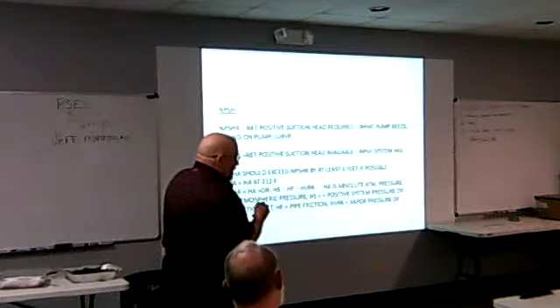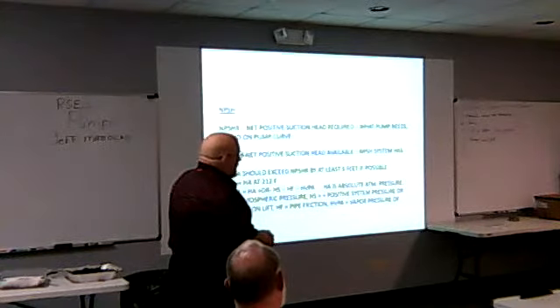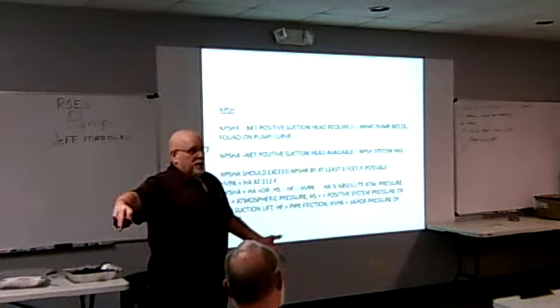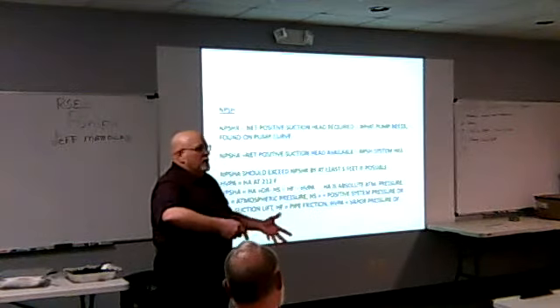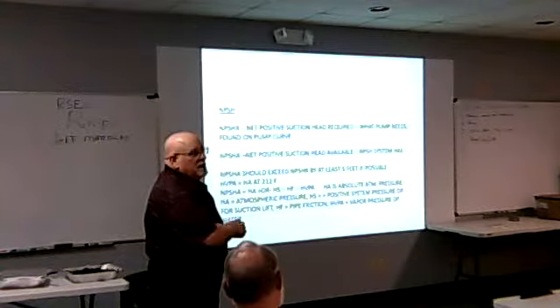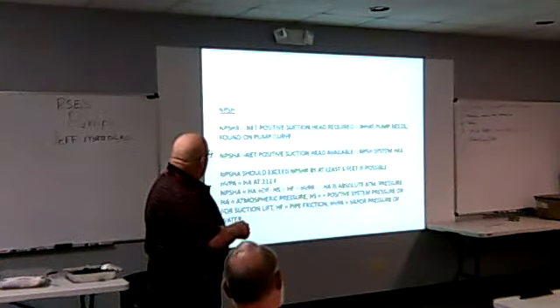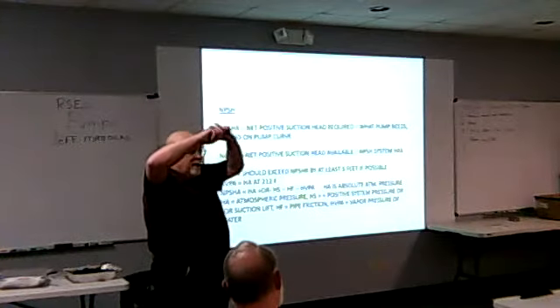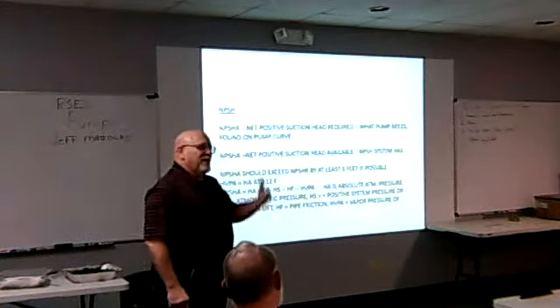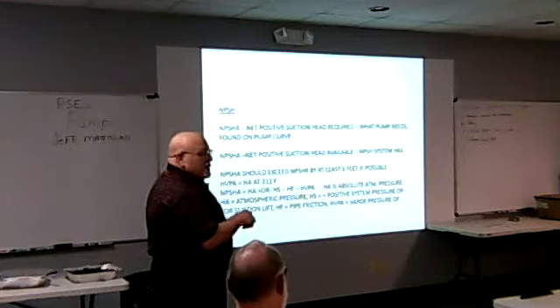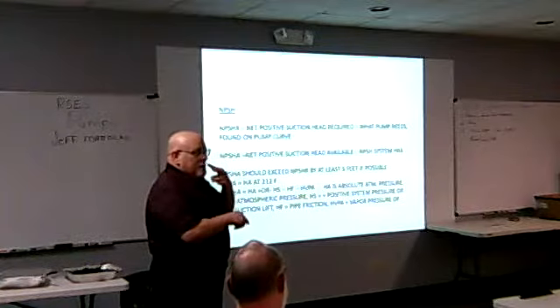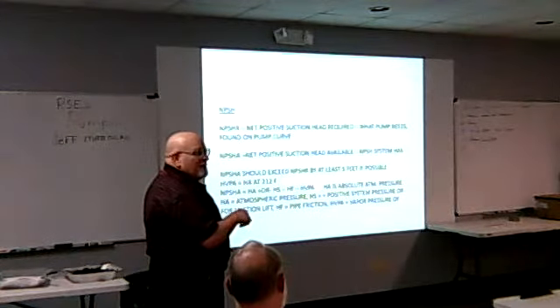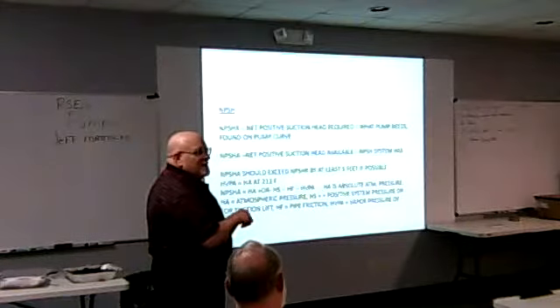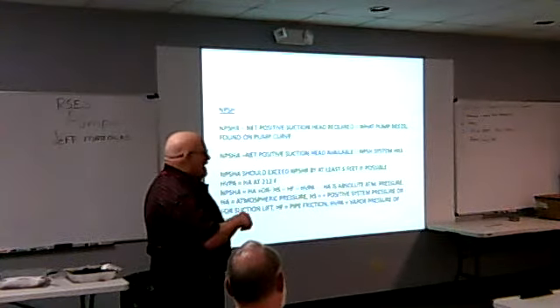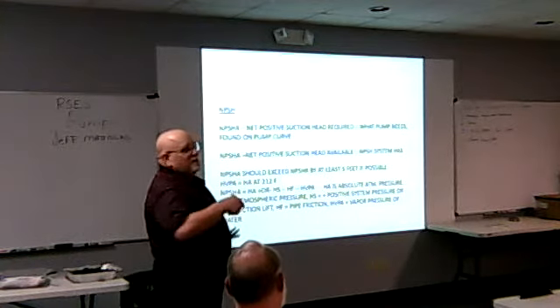What will change in your NPSH equation? Here's the equation right here again. This is atmosphere. So like I said, in a closed loop, I have atmosphere plus fill pressure. That's what I'm starting with. If I have an open cooling tower, all I have is 14.7 PSI, or 33 feet of head, plus or minus any elevations I have. If the tower's 20 feet up, that's giving me good head. If I'm lifting 6 feet, it's going the other way. Plus or minus my frictional losses, minus my vapor pressure. Again, a heating system, boiler, where it's open to the atmosphere at 200 degrees, we've got a problem. Chilled water, closed loop, no big deal. Heating, this number gets real big, but I've got atmosphere plus 30 pounds.